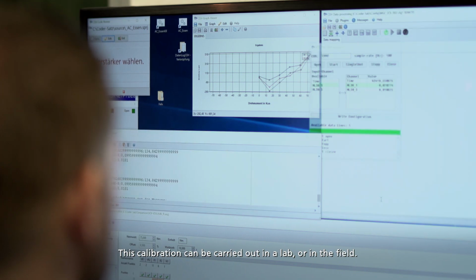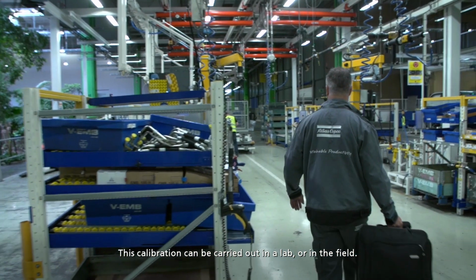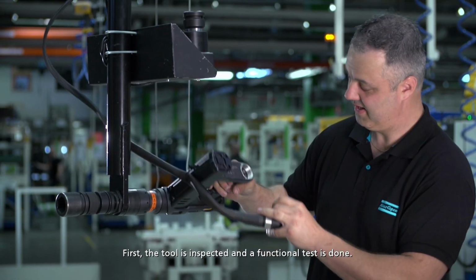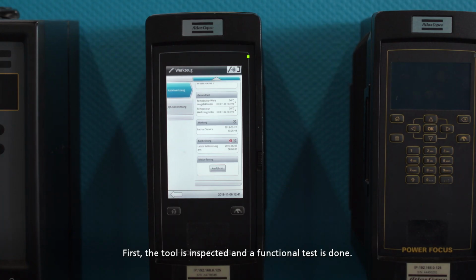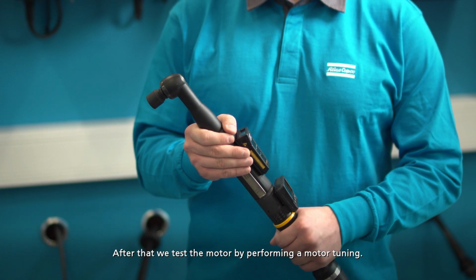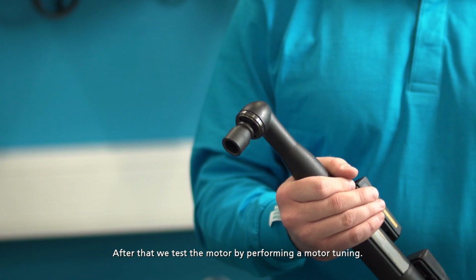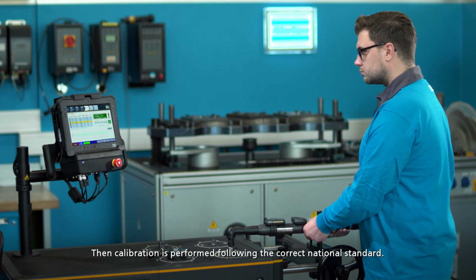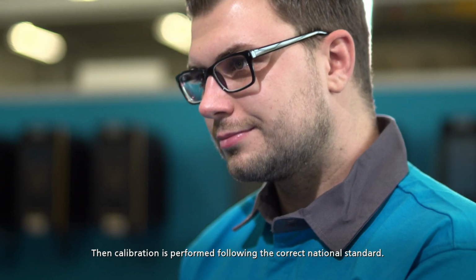This calibration can be carried out in a lab or in the field. First, the tool is inspected and a functional test is done. After that, we test the motor by performing a motor tuning. Then calibration is performed following the correct national standard.